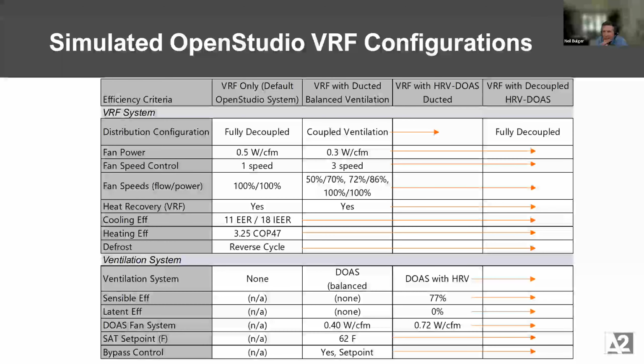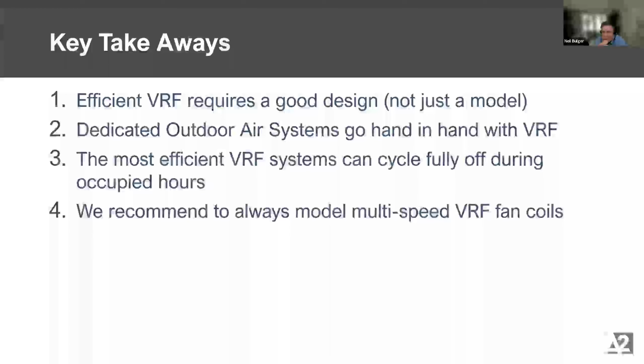So that's, and we can take some more questions, but that's generally the example I wanted to run through here. I would say some key takeaways are that efficient VRF requires a good design, not just the model. You can definitely represent key things, though some of what will drive efficiency is really hard to put in the model. The pipe length item, hard to represent.